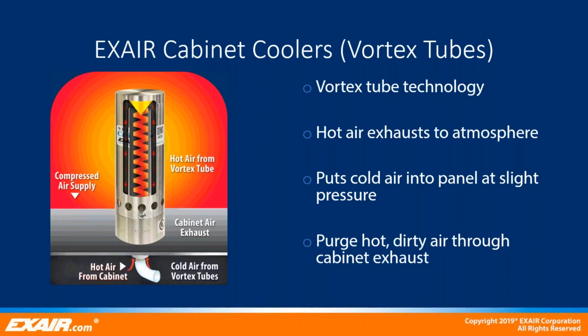Now on to EXAIR Cabinet Coolers. How do cabinet cooler systems work? Compressed air enters the vortex tube powered cabinet cooler and is converted into 2 streams, one hot and one cold. Hot air from the vortex tube is muffled and exhausted through the vortex tube exhaust. The cold air is then discharged into the cabinet through the included cold air distribution kit. Then the displaced hot air in the cabinet rises to the exhaust to atmosphere through the cabinet cooler body. The control cabinet is then both cooled and purged with cool, clean air. Outside air is never able to enter the control panel.